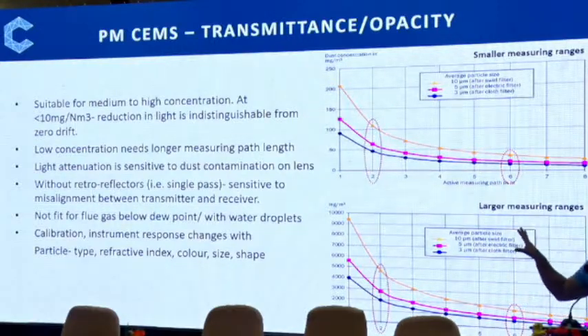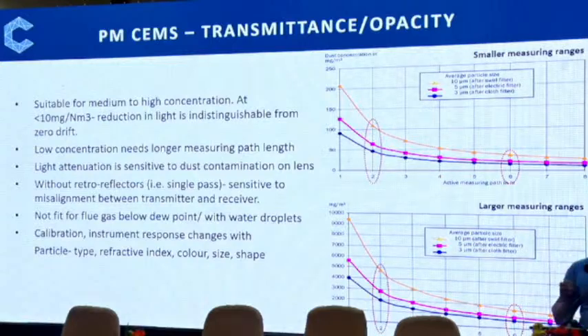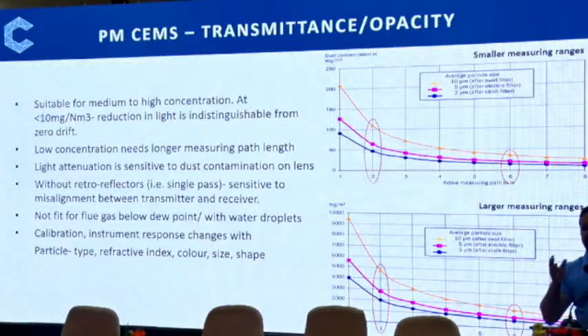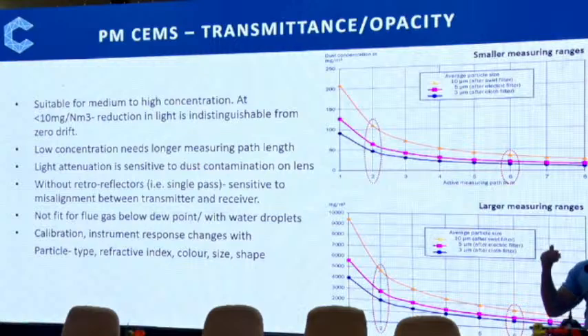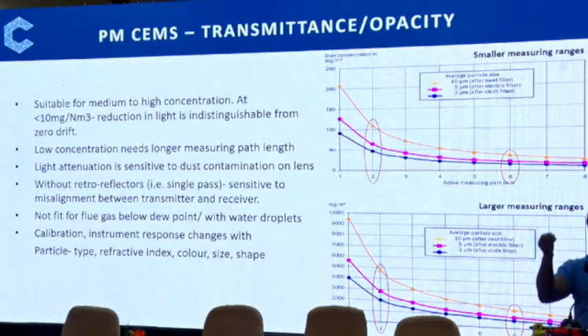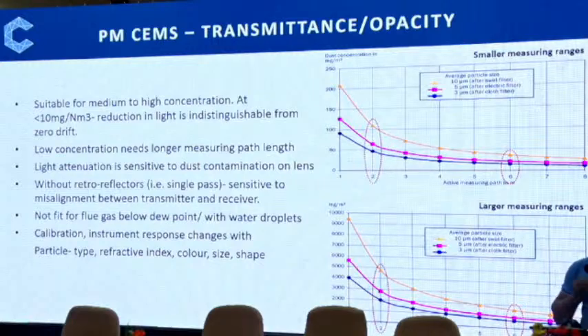All these technologies work on optics or light, which can be affected by moisture droplets, particle sizes, different particle shapes, refractive index, etc. But normally in our power plants or in any industry when we combust, it's a mixed particle. It's not like we get a particular type of particle going through. So that may not be much of a problem, but it matters when you have an ESP working at certain efficiency. Largely, particle size and mix is not a problem because we have a mix all the time. Calibration and instrument response design change with the particle type and refractive index, but you cannot get into that much detail.